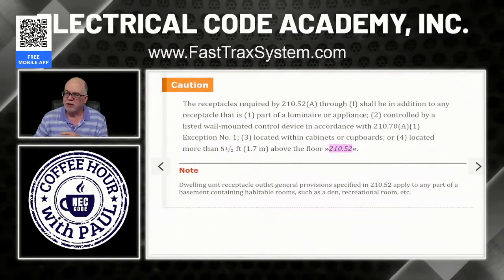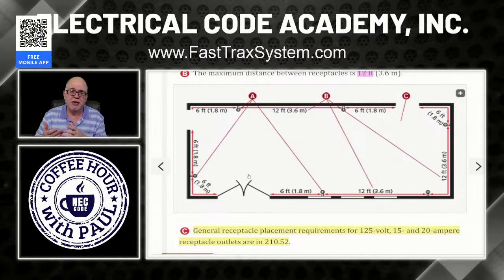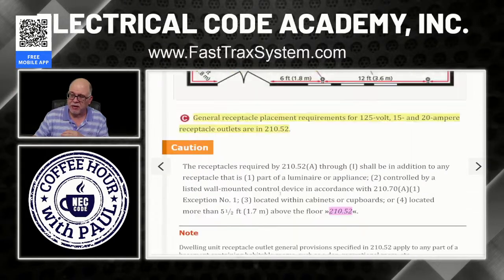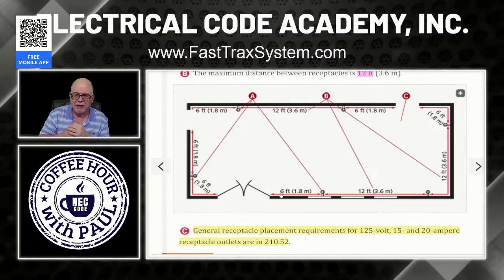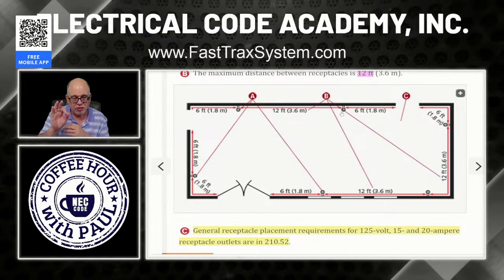Now, the next one, controlled by a listed wall-mounted control device in accordance with 210.70A1, exception number one. So what does that mean? Let me give you an example. Your bedroom. Maybe you don't want to have a light in the ceiling. Well, the exception under 210.70A1 says, you know what? I'll let you switch a receptacle in lieu of a lighting outlet. But you can't switch the whole receptacle. Why? Because it wouldn't meet the 210.52 spacing requirement. It has to be a receptacle that's there, powers on all the time, not where you can switch it off.